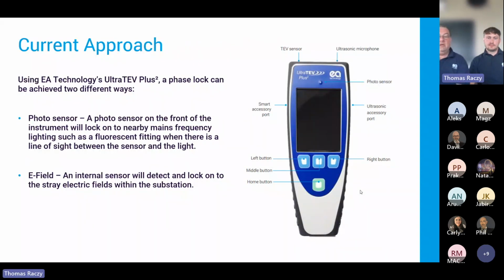The unit we're talking about with the handheld instruments, just to make sure that people aren't thinking of our older instruments, is the UltraTEV Plus2. This has built into it a photo sensor which locks onto available frequencies in the substation where you're doing the survey. It also has alternative ways of locking on, such as the E-field, and I will reference how people have come back to us about this phase lock at a later time.